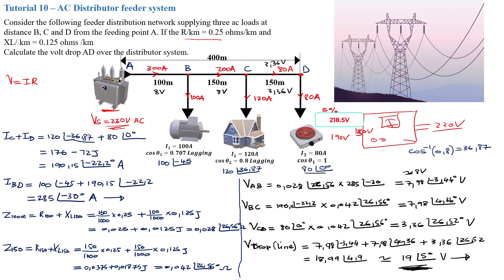Now we don't know what was the voltage here that was sent, we don't have that information. But now assume that this was indeed 230 volts. Then you have to minus the 19 volts because remember you're sending a voltage at an angle, it's always going to have an angle of zero degrees. So 230 volts minus this 19 here, you're going to expect a voltage here of about 211 volts.